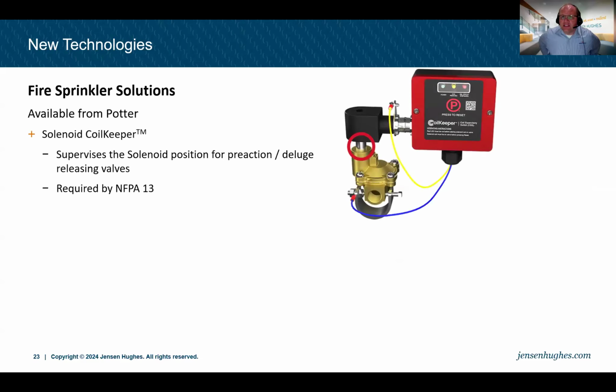NFPA 13 requires that if we have a solenoid that's controlled by a fire alarm system, for instance, for a pre-action sprinkler system or a deluge sprinkler system, where the fire alarm is releasing the valves, they do it through a solenoid. Well, it's now required by NFPA 13 that that solenoid is monitored. And so we know if that solenoid is actually on the releasing valve, actually on the device that does it. So if that solenoid is removed from that piston or from that actuator, it illuminates an audible and visual alarm. And we know that that system is no longer capable of doing its releasing.